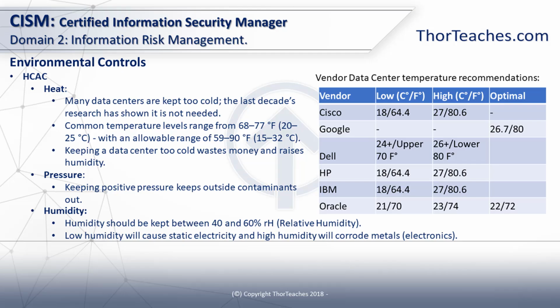I worked in a data center at some point that was pretty clean, but they didn't do the annual cleaning on the subfloors. The subfloor is where they ran all the cables, so they had a good 1.5 feet or about 50 centimeters between the actual floor and the floor the data center was on. You then have a metal grid structure with tiles you can remove, and the tiles in the appropriate places are perforated so the air can get pushed up in the cold aisles and stay beneath the floor in the hot aisles. I'll show you some graphics on it later so you have a better idea of how it works.